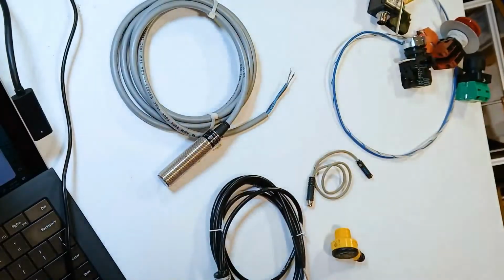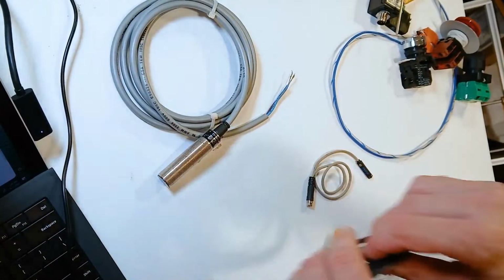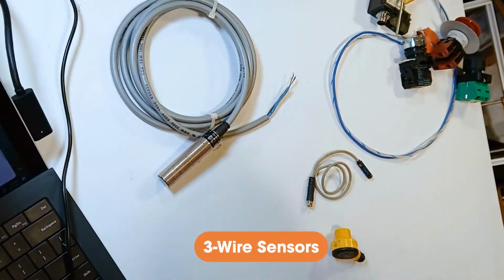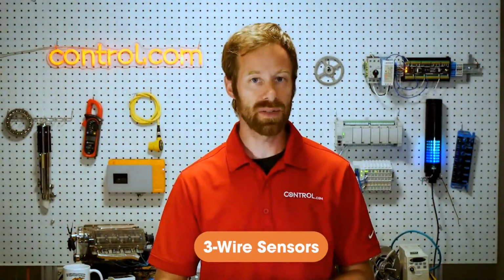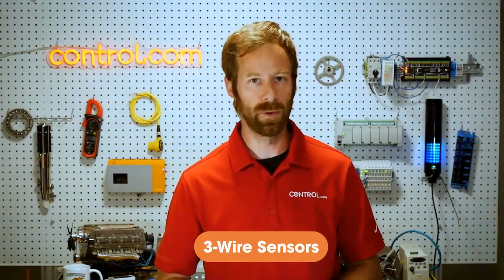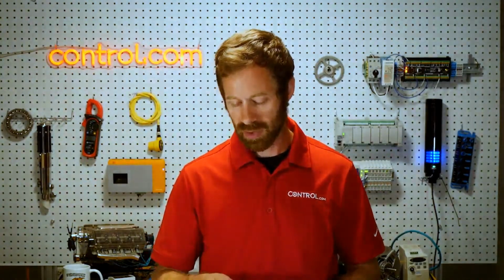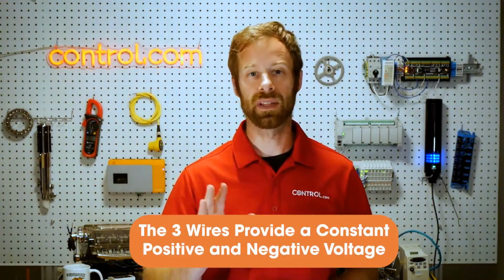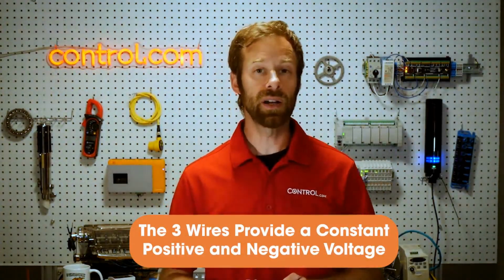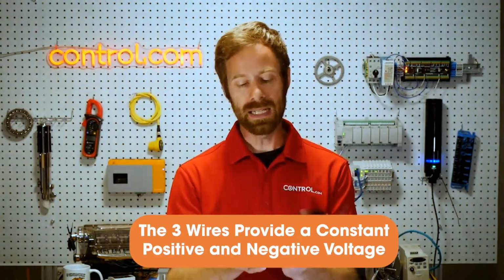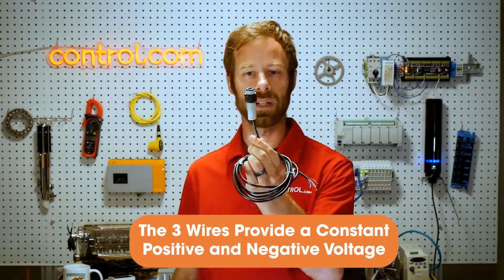A bit more commonly, there are these sensors that are called 3-wire sensors. It's a bit of a misnomer here because 3-wire sensors might actually often include 4 wires, but 3 of them are the most critical. Let's talk about those 3 wires in these distance sensors or optical sensors, proximity sensors, this whole wide range. These 3 wires have the function first of providing a constant positive and negative voltage. Providing a constant positive and negative voltage means that inside the sensor we can power some electronics.